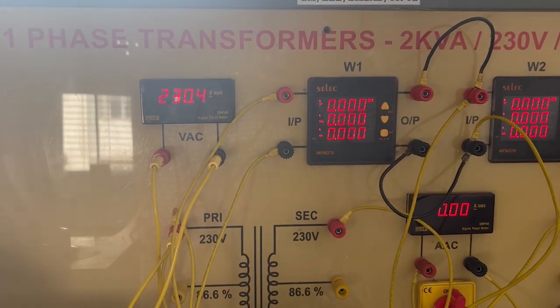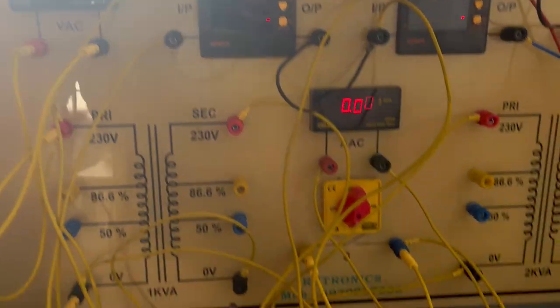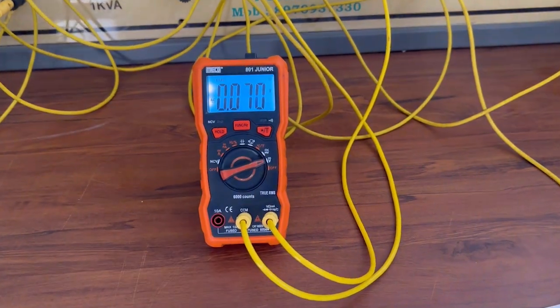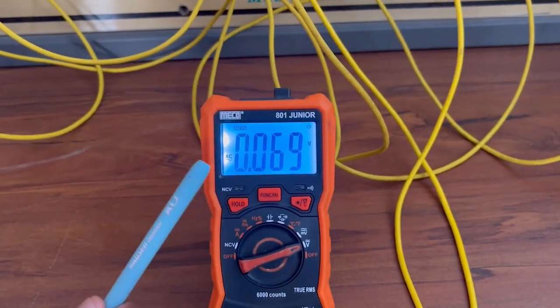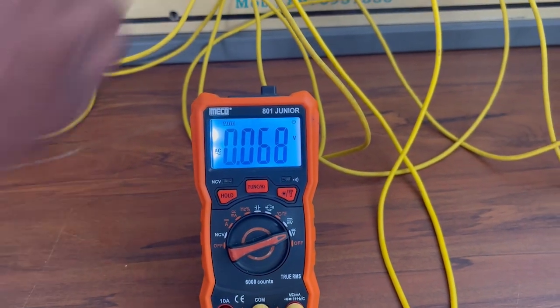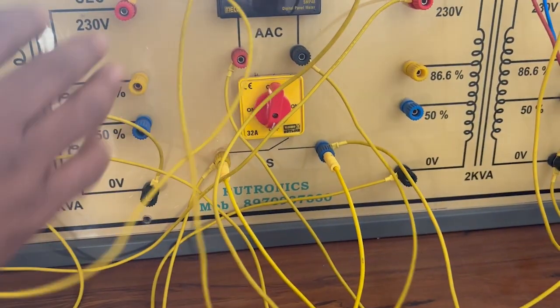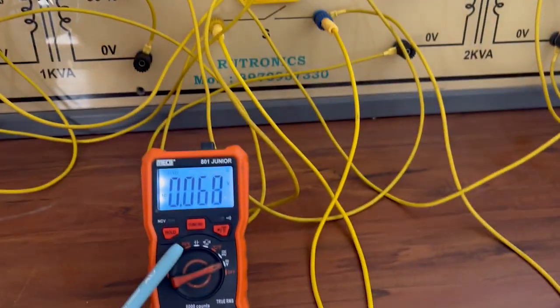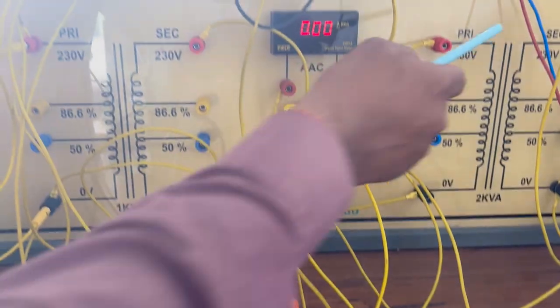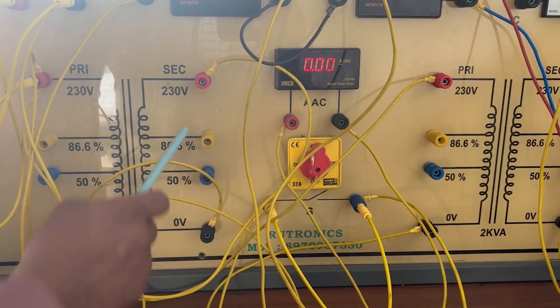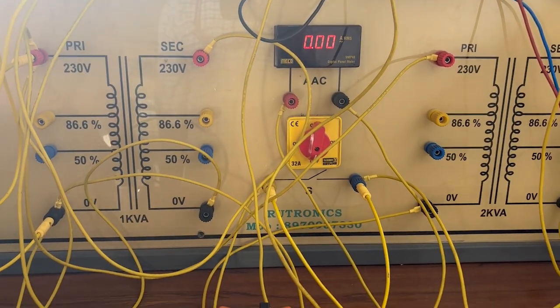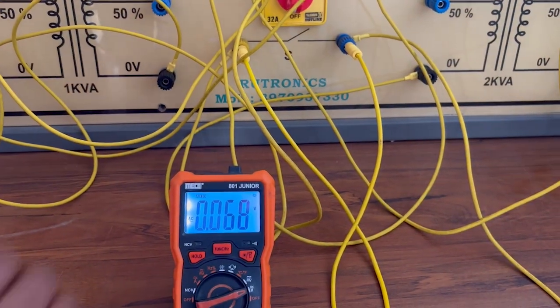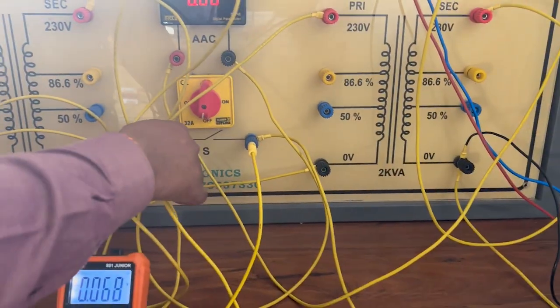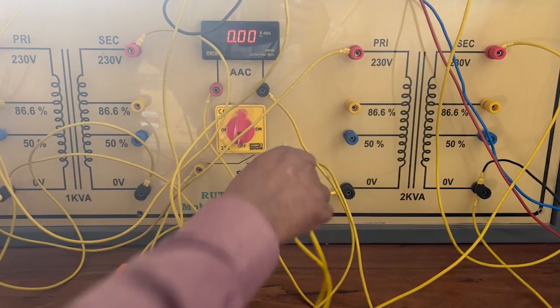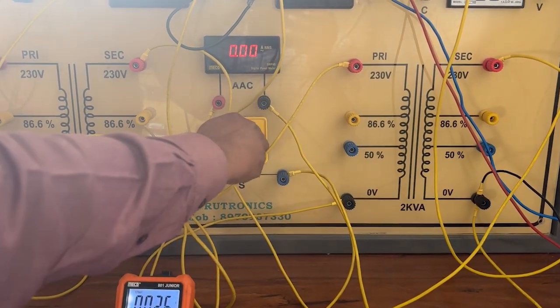Right, after setting 230 volts, you have to check with the multimeter. If the multimeter reads 0, then you can close the switch. This is the switch. If it reads double the voltage, then you have to interchange the secondary terminals of any one of the transformers. Now it reads 0. Now we can close the switch. We have to disconnect the multimeter terminals. Then close the switch.